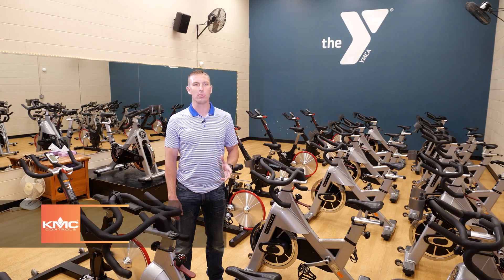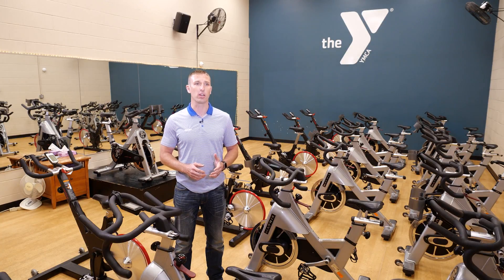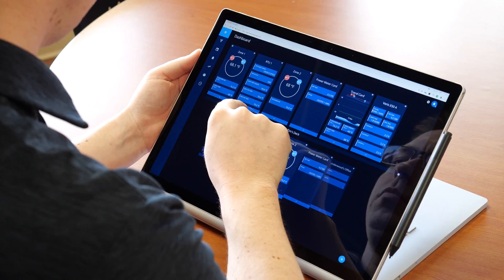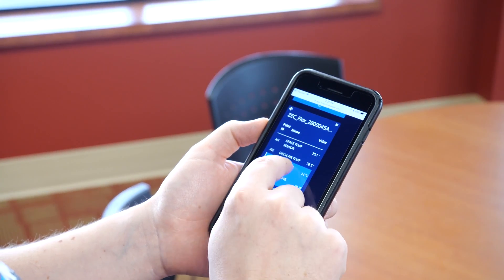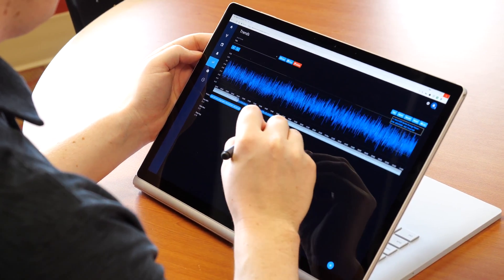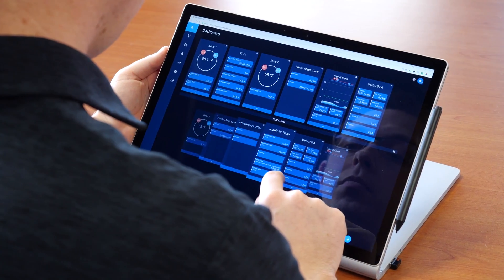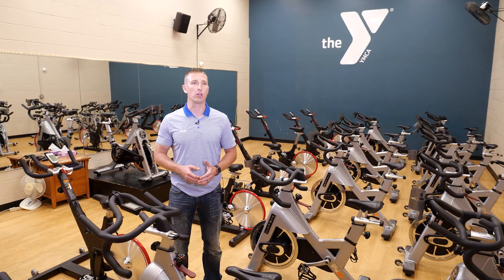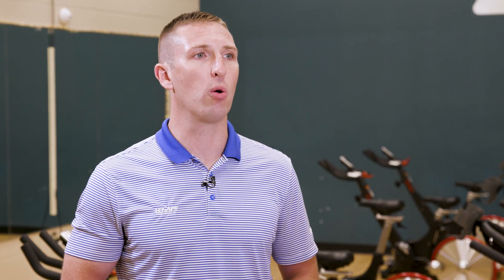I'm a numbers guy. I enjoy being able to analyze system performance and identify areas for operational improvement. That's why we feel that the partnership with ECO has been such a great success — they speak the same language as us. They're focused on delivering healthy, well-performing buildings and client comfort. And when they use KMC Commander, they're doing just that. The platform gives users at multiple permission levels the ability to view and control the building remotely, whether it be a phone or laptop. It's extremely versatile, and the metrics it's able to provide are just as versatile. If they want to visualize energy usage data such as cost per square foot, they can add that to their dashboard. They can also create their own metrics by accessing published API data from sources such as the National Weather Service, in case they're interested in weather normalization. Then if they wanted to aggregate and trend that data across a portfolio of buildings, that's easy. This helps them provide predictive maintenance and prioritize site upgrade requirements. They can also utilize automated reporting to export site data on a recurring basis. Alarming is supported via email, text, or push notifications to let them know when there's an issue or when service is required.